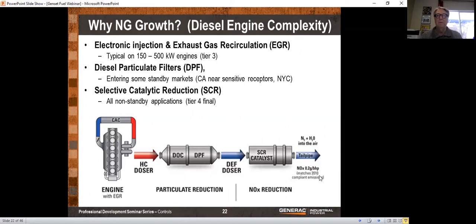And with standby generators, typically that doesn't happen. They start up, they run for maybe 20 minutes at no load, and then they go down, and this particulate filter never gets hot enough. So you physically have to go in with your hands and clean out all of that soot periodically if you have a diesel particulate filter.